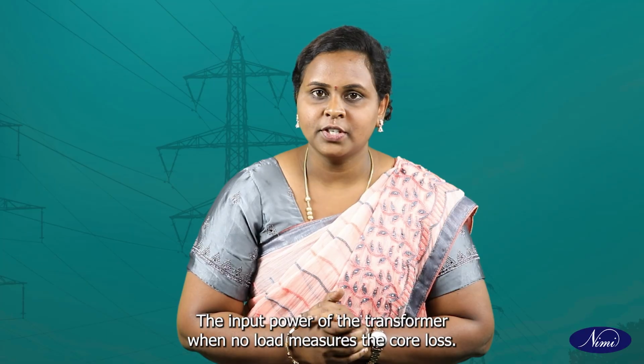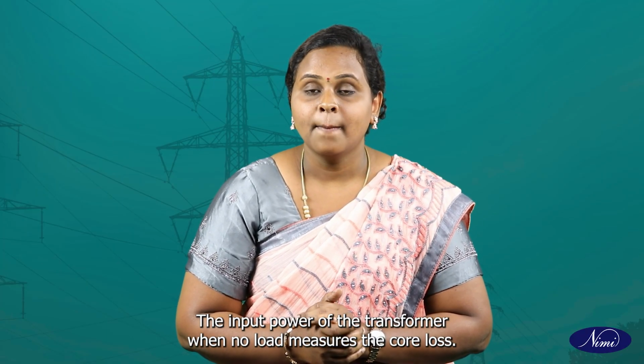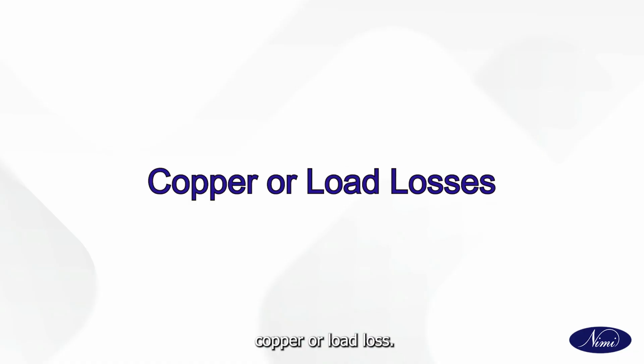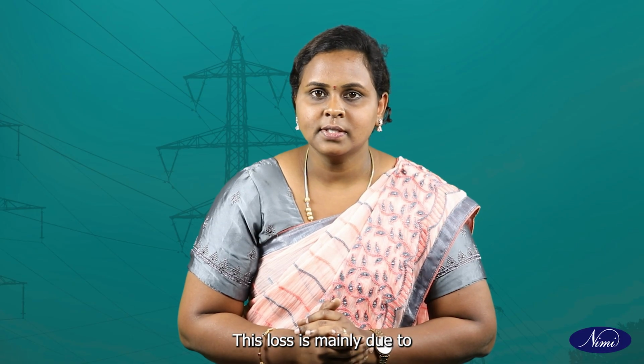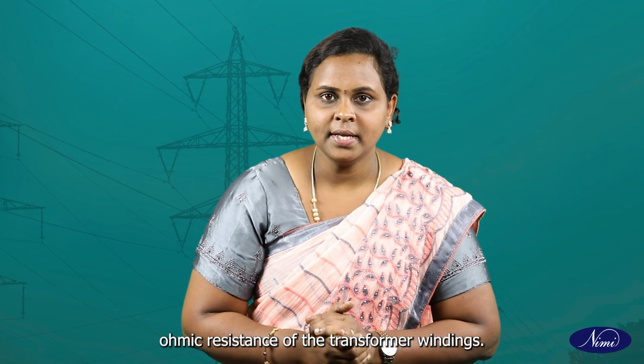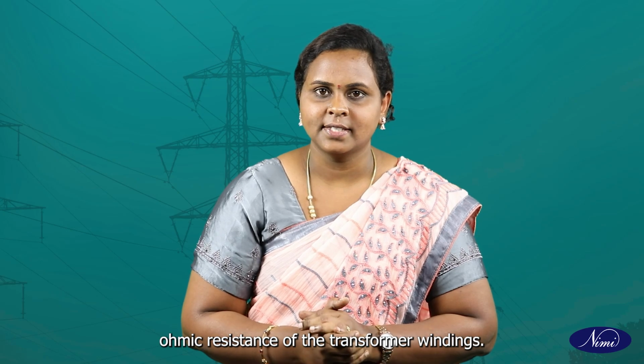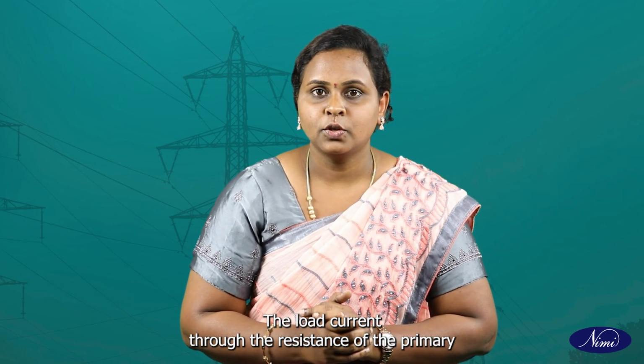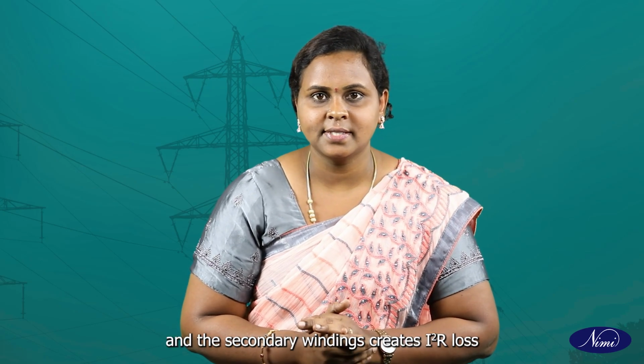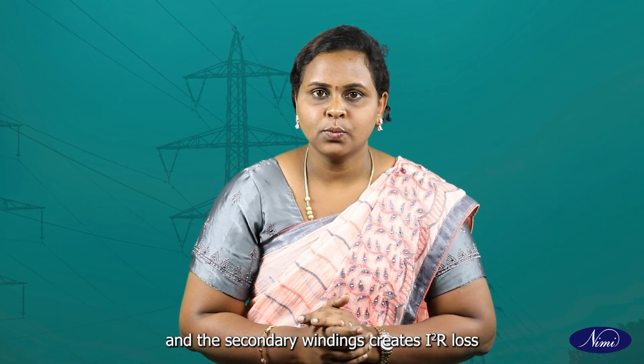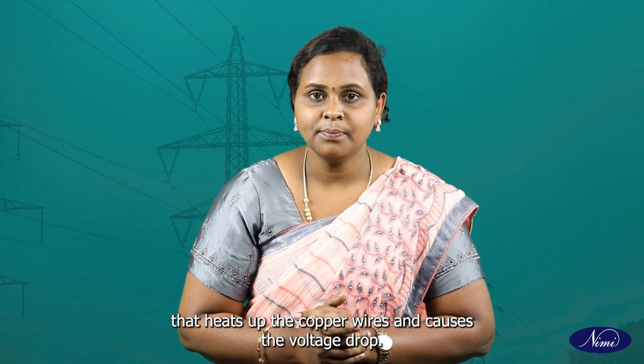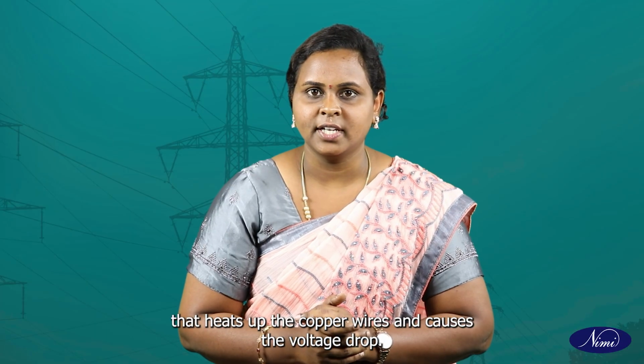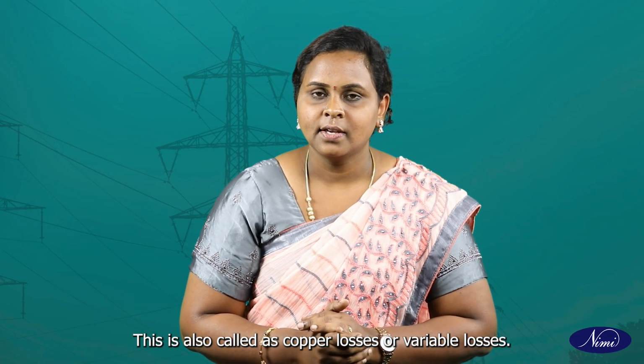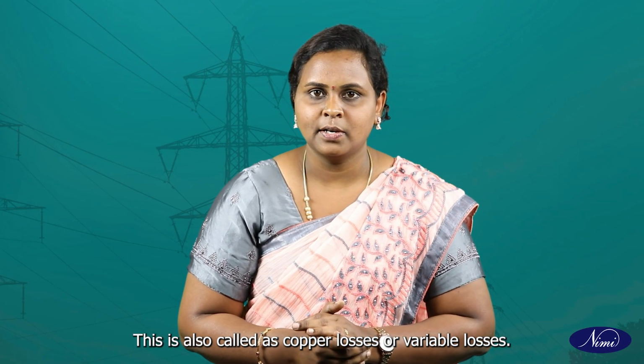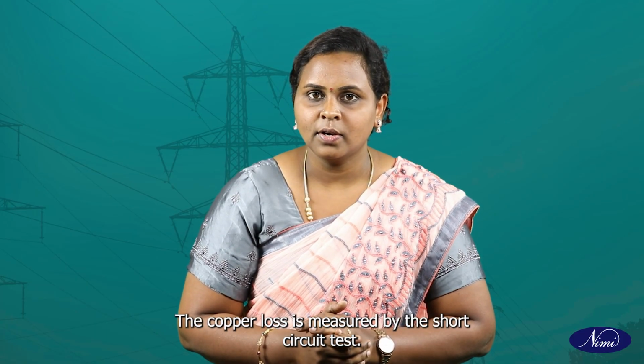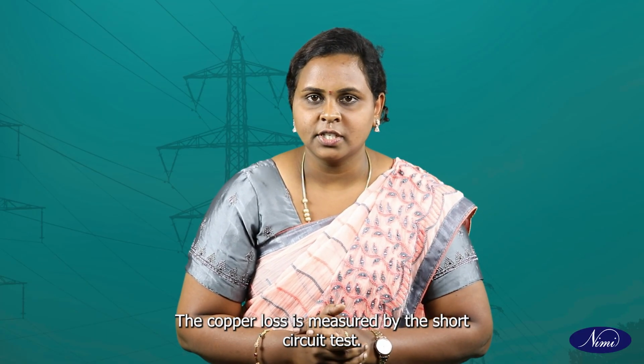The input power of the transformer at no load measures the core loss. Copper or load loss is mainly due to the ohmic resistance of the transformer windings. The load current through the resistance of the primary and secondary windings creates I square R loss that heats up the copper wires and causes voltage drop. This is also called copper losses or variable losses. The copper loss is measured by the short circuit test.